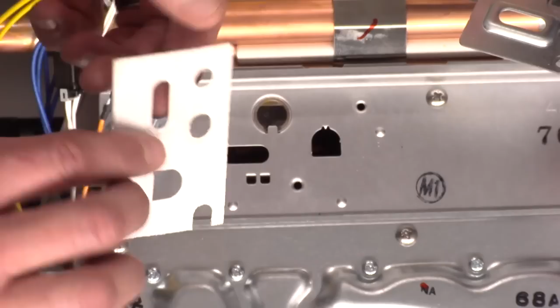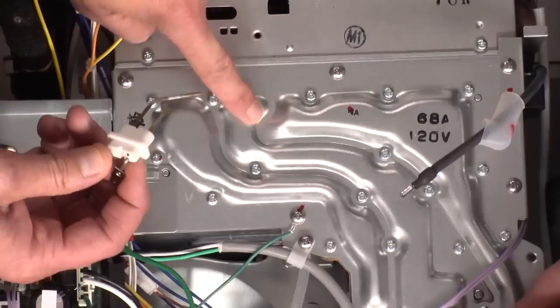Let's talk about the igniter and flame rod. Now, the flame rod is there to sense the flame. Your flame rod is the longer piece, and it's actually over this middle chamber in your manifold. That's what's going to light first. When we light the gas here, we've got to be over that middle chamber, and we're going to sense flame.